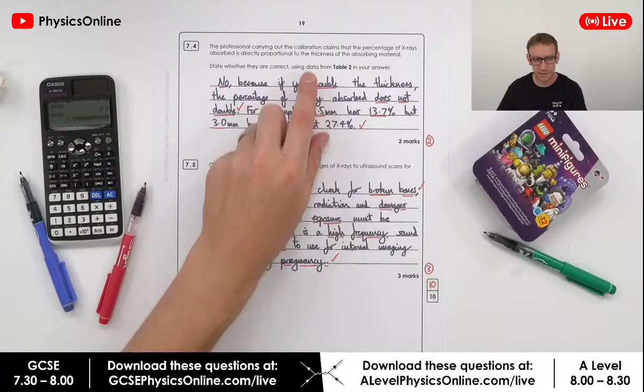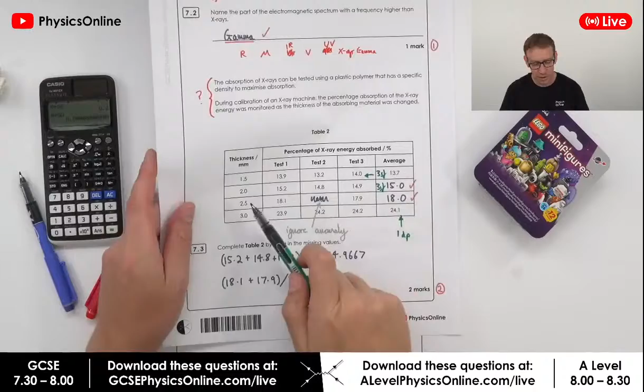The professional carrying out the calibration claims that the percentage of X-rays absorbed is directly proportional to the thickness of the absorbing material. When we have something which is directly proportional, if we were to plot the data on a graph, we would have a straight line that goes through the origin, and that would mean the two things are directly proportional. However, if we look here, if we double the thickness from 1.5 to 3, the average was 13.7, and now the average is 24.1. So it hasn't doubled. If it really was a directly proportional relationship, it would go from 13.7 to 27.4, which it didn't. So if you were to plot this data, you wouldn't get a line like this. Instead, you might get a line like this.